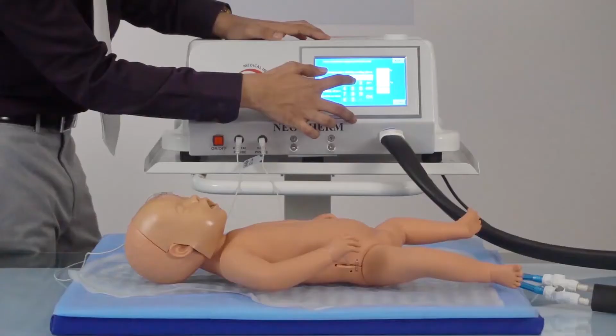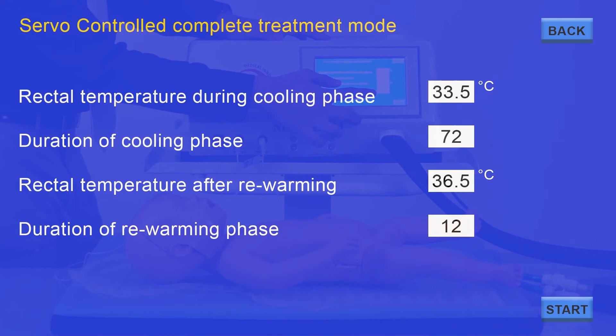In the next step, we set the duration of cooling to be 72 hours as standard. The rectal temperature for the rewarming phase is to be set at 36.5 degrees. The duration of the rewarming phase can be set as desired or the standard of 12 hours. Once you are done with the settings, you may click on the start button and start the therapy.